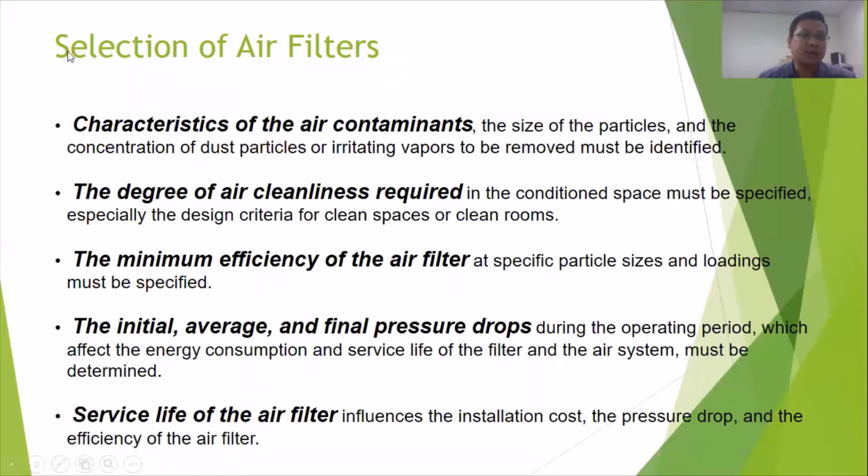Okay, so now we go to how to select a filter. This one considers parameters which will be measured on how to select a filter in the application. The first parameter should be the characteristics of the air contaminant: the size of the particle and the concentration of the dust particle or irritating vapor to be removed must be identified.